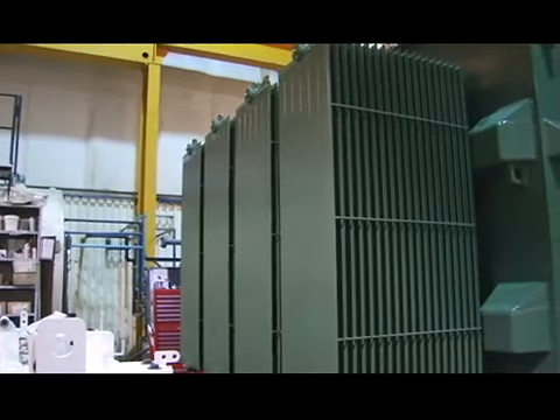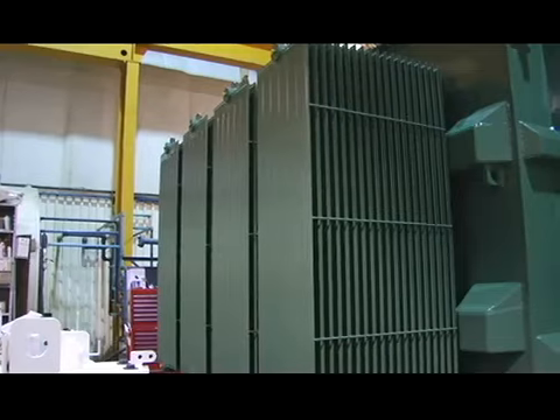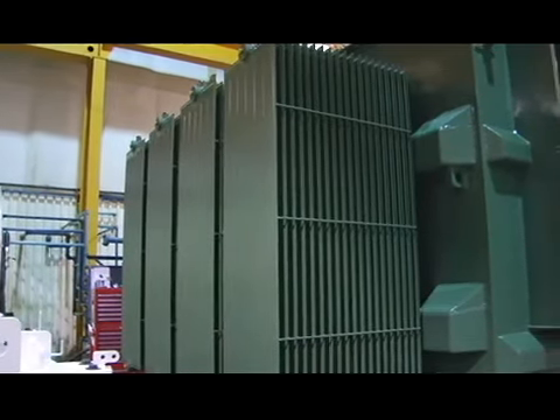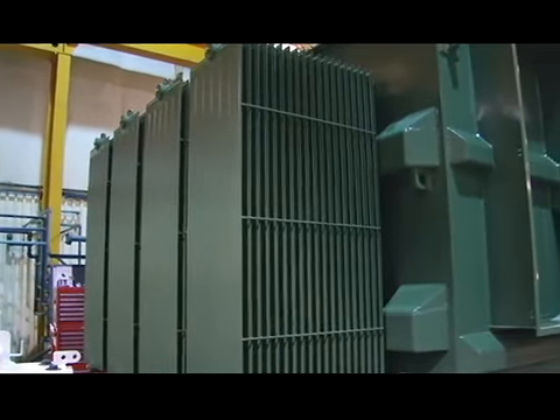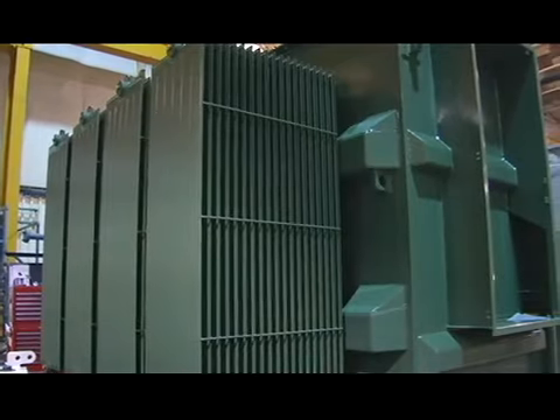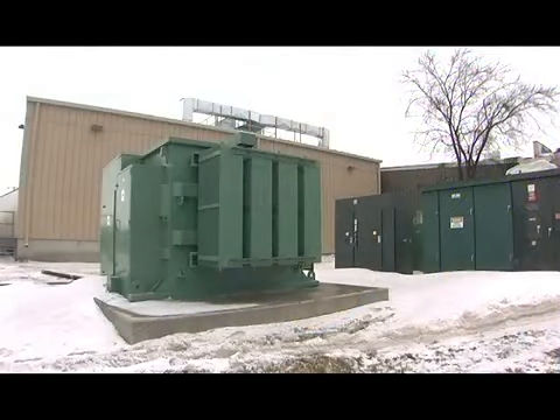The high voltage Padmount transformer uses sealed tank construction. This design greatly reduces the cost of maintenance throughout the life of the transformer. The newer designs of these transformers are all dead front, so there's no bushings that need cleaning. The high voltage compartment is all protected from the weather by the cable entrance compartment.